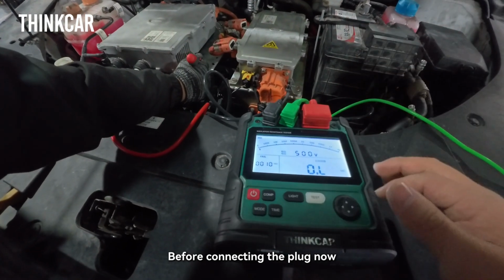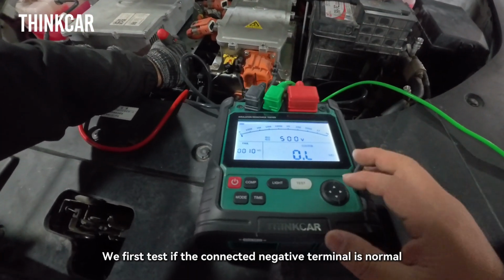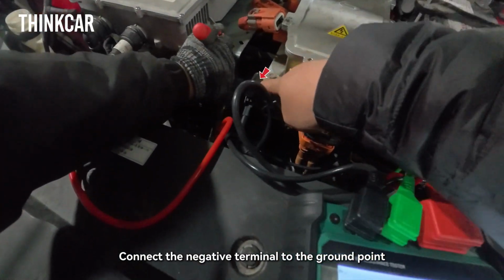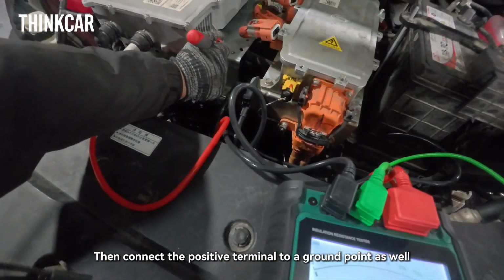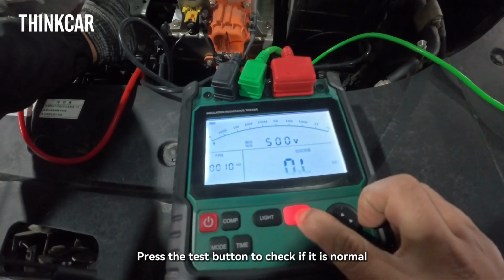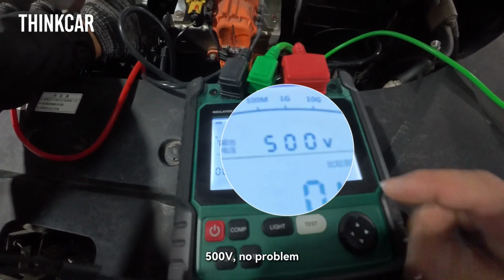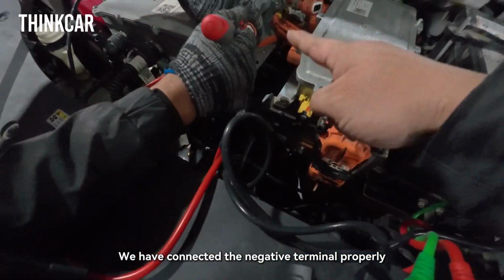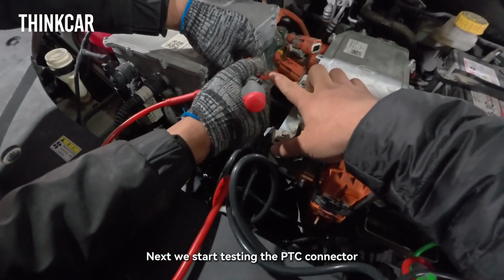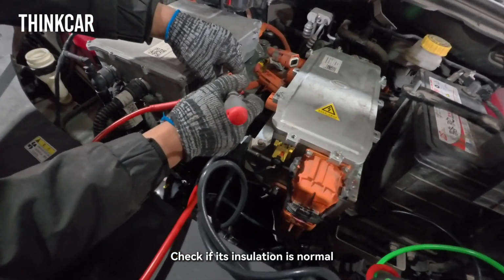Before connecting the plug now, we first test if the connected negative terminal is normal. Connect the negative terminal to the ground point, then connect the positive terminal to a ground point as well. Press the test button to check if it is normal. 500V, no problem. We have connected the negative terminal properly. Next, we start testing the PTC connector. Check if its insulation is normal.